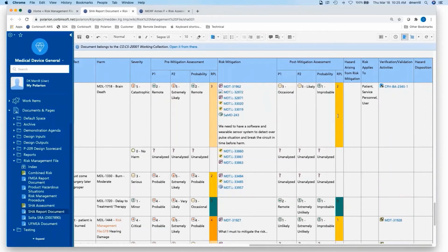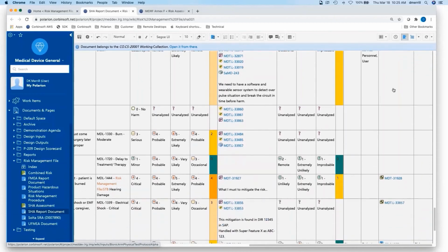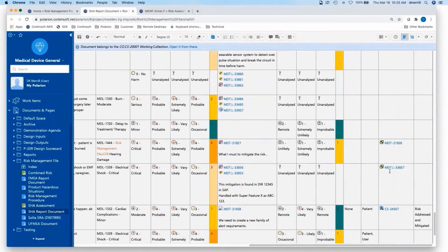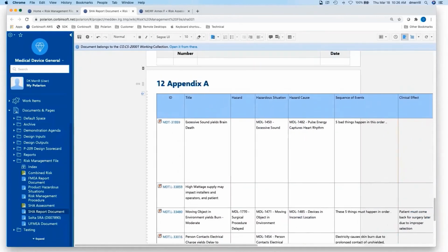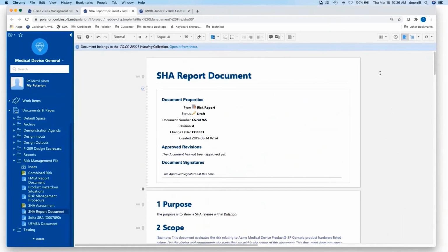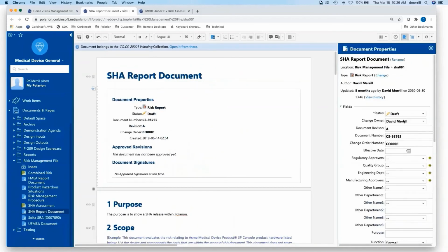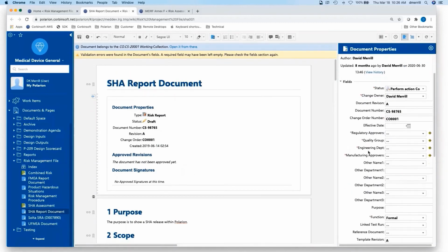Well, it's done by these requirements, and these requirements are verified in a particular protocol. And we can show the association of that traceability either at the protocol document level or directly to the test itself. I know this is kind of a fast look into a very complex process, but what we want to be able to do once we've accumulated this information is move it from draft to the ability to collaborate and include individual users in this document.